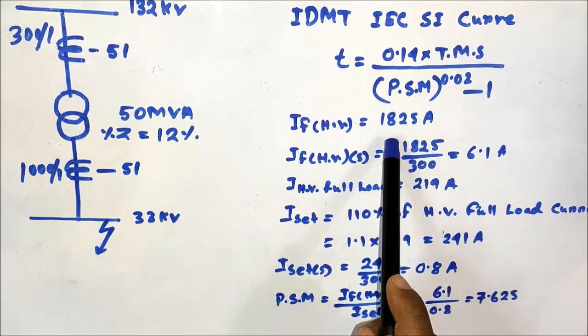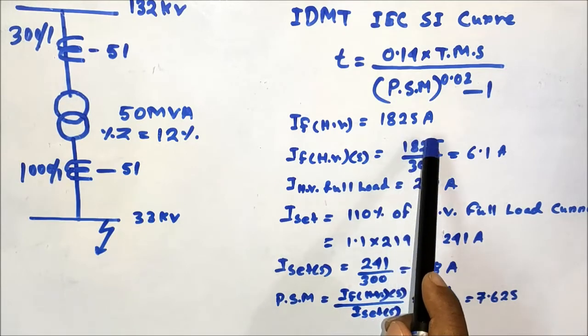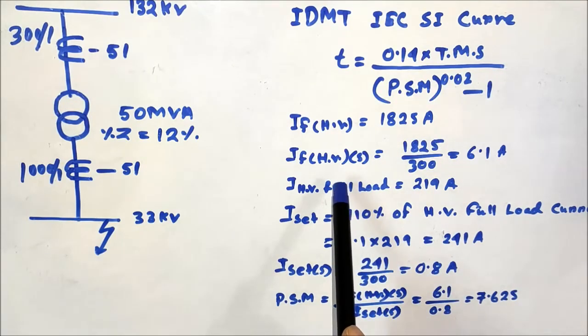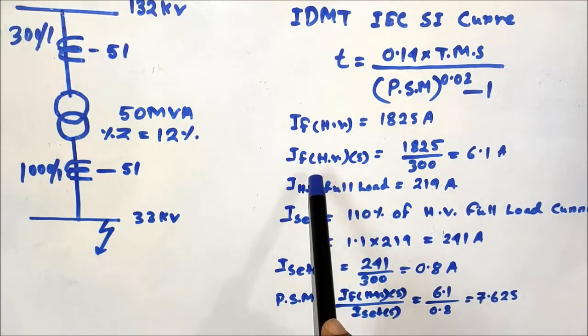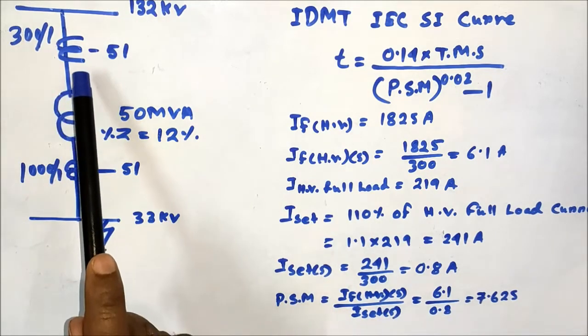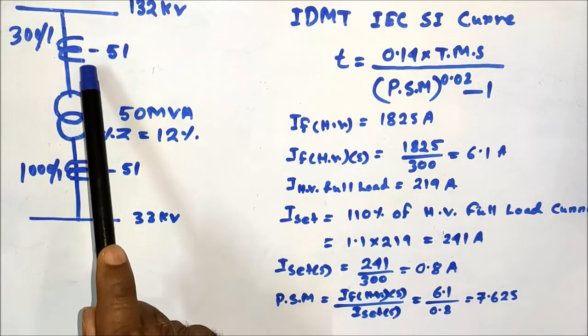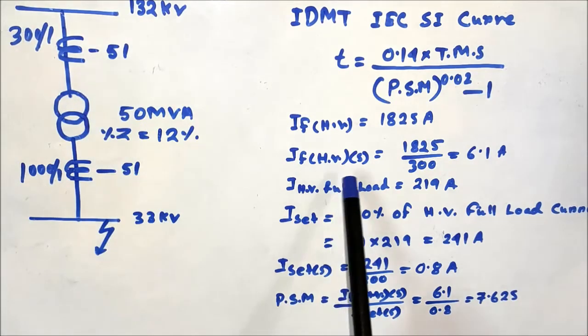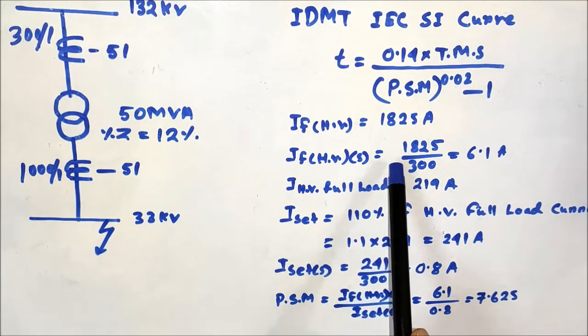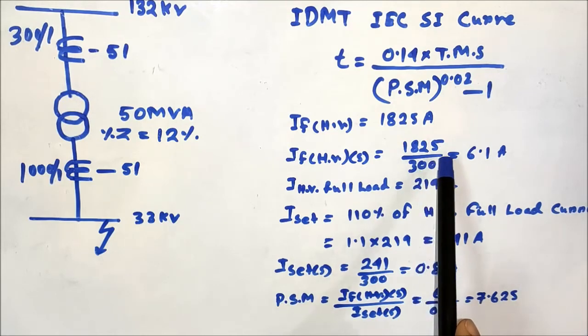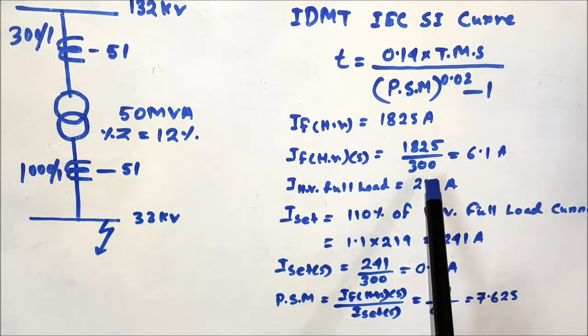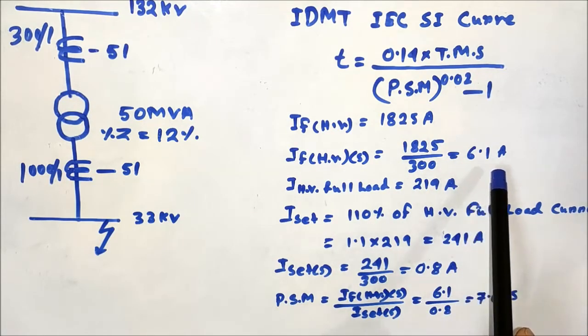The fault current on the HV side is 1825 amperes, or 1.825 kilo-amperes. The CT ratio on the HV side is 300/1. The fault current sensed by the relay, connected on the secondary side of the HV CT, is 1825 divided by 300, which equals 6.1 amperes.